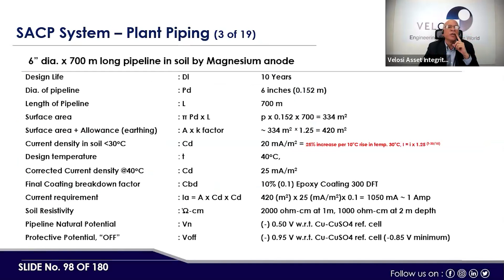Surface area is pi d L. Then surface area allowance for earthing is A into K factor. Then current density in soil, which is here 20 milliampere per meter square, with a 25% increase per 10 degree Celsius rise in temperature. This equation has to be done. Then design temperature is 40 degrees Celsius, and corrected current density at 40 degrees Celsius is 25 milliampere per meter square.